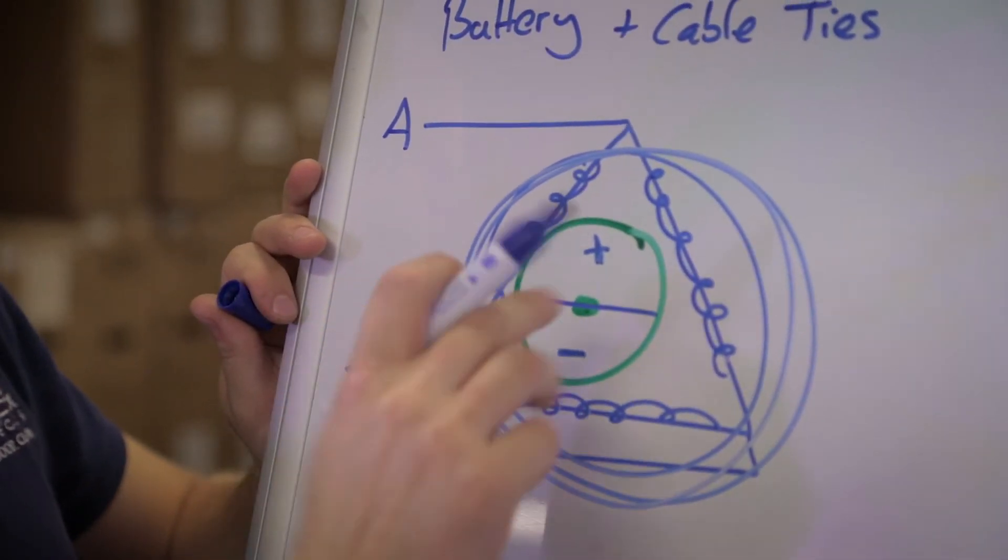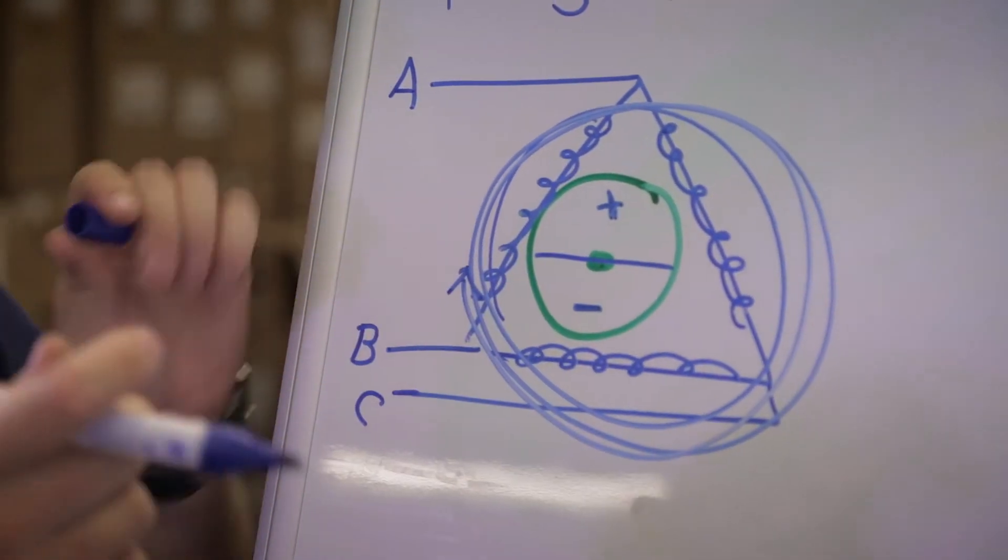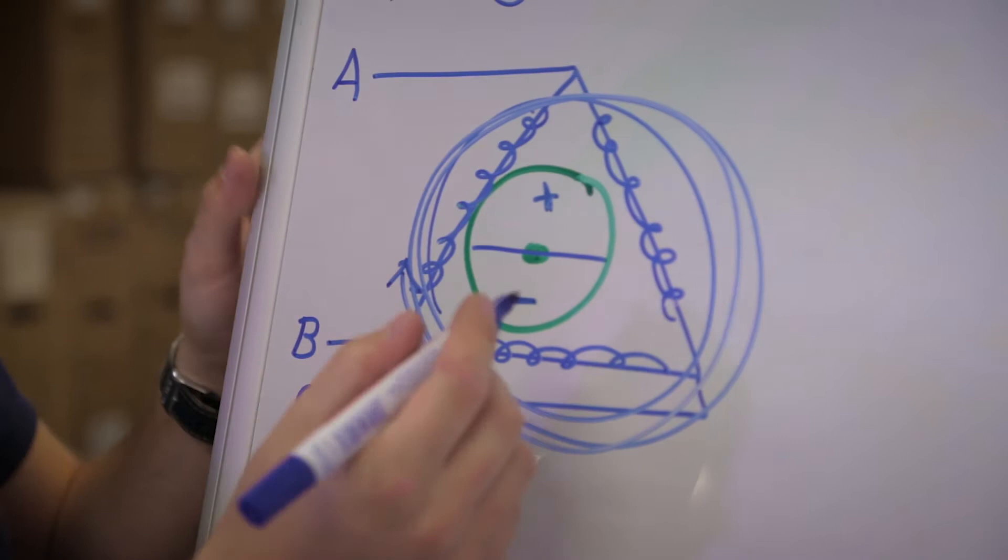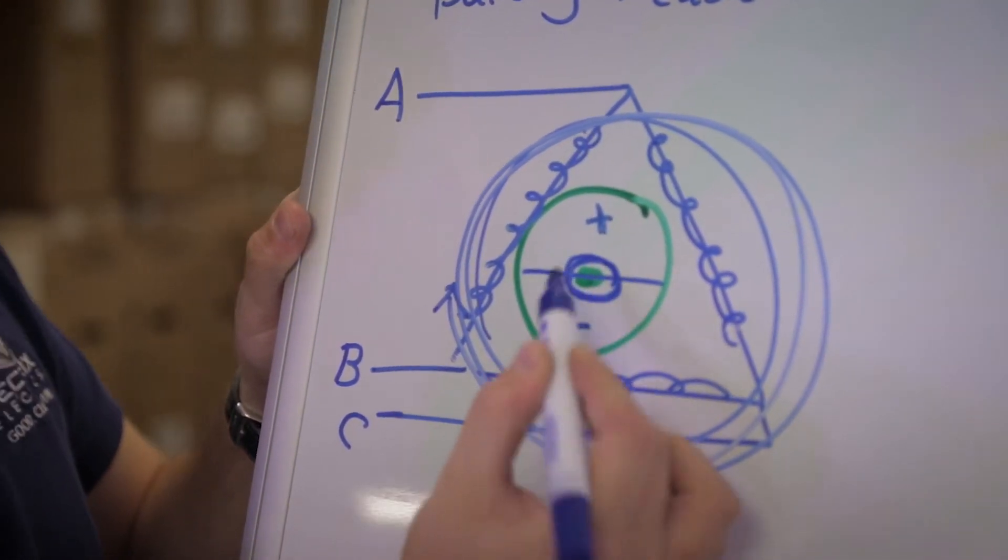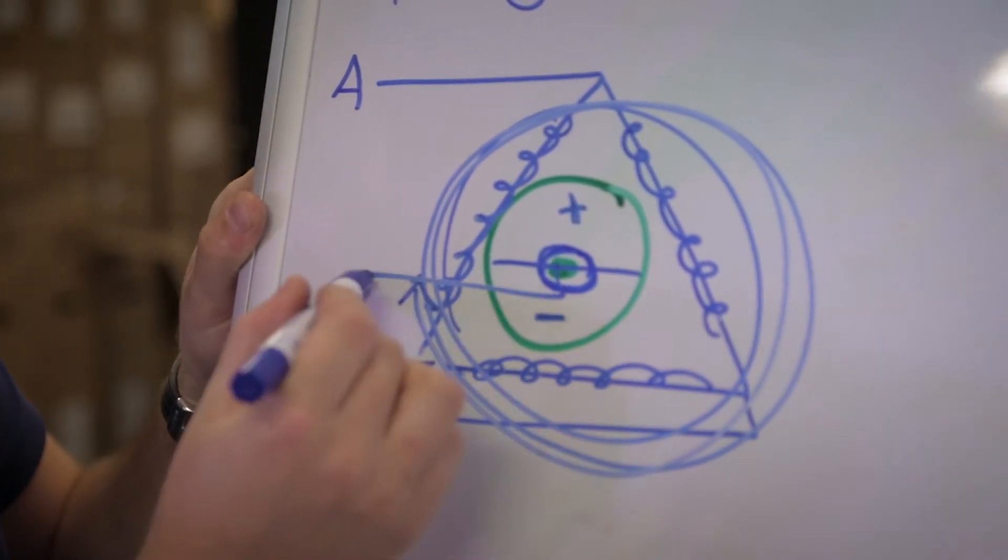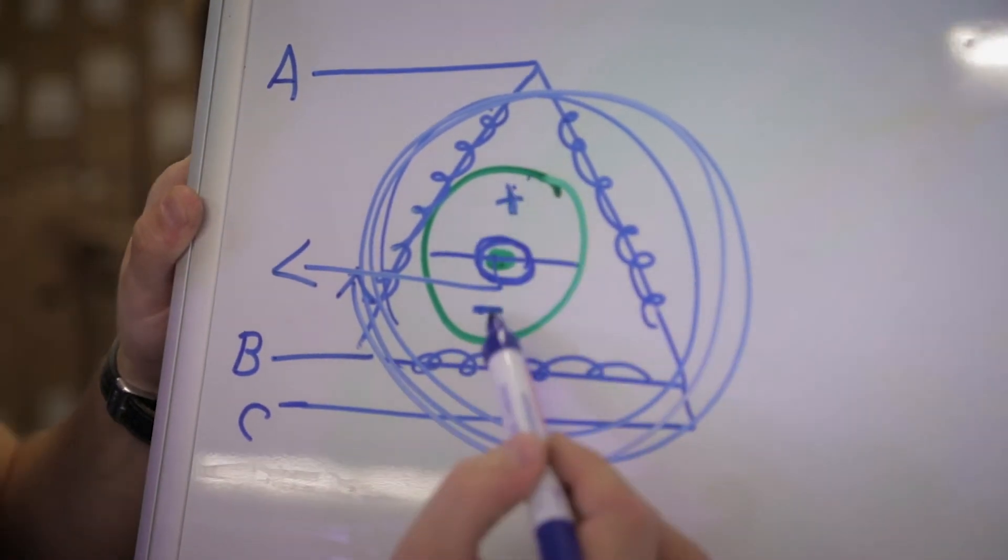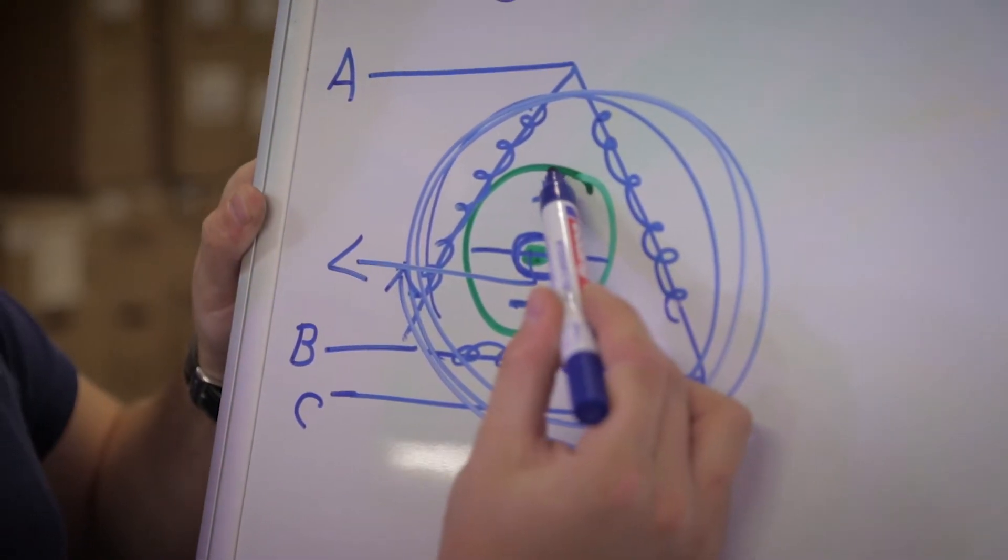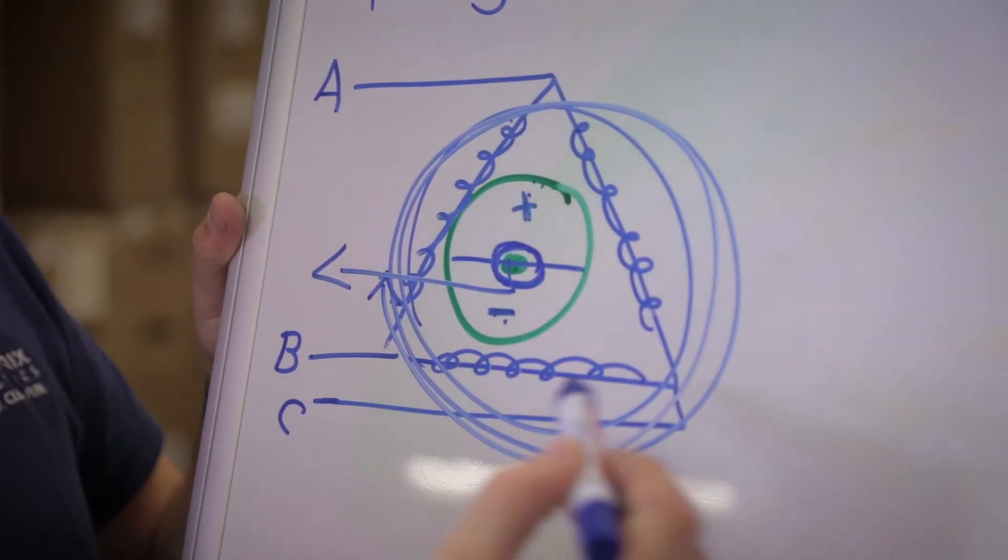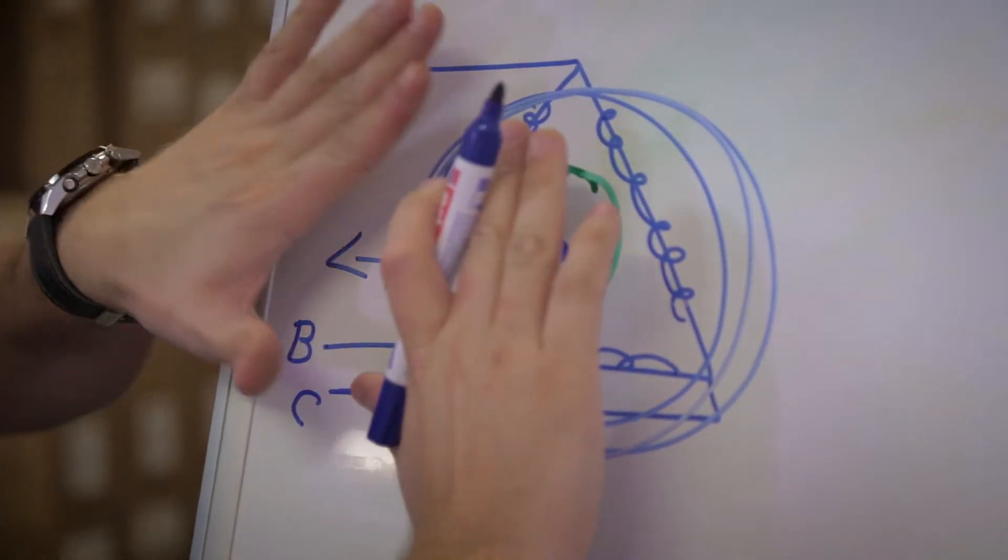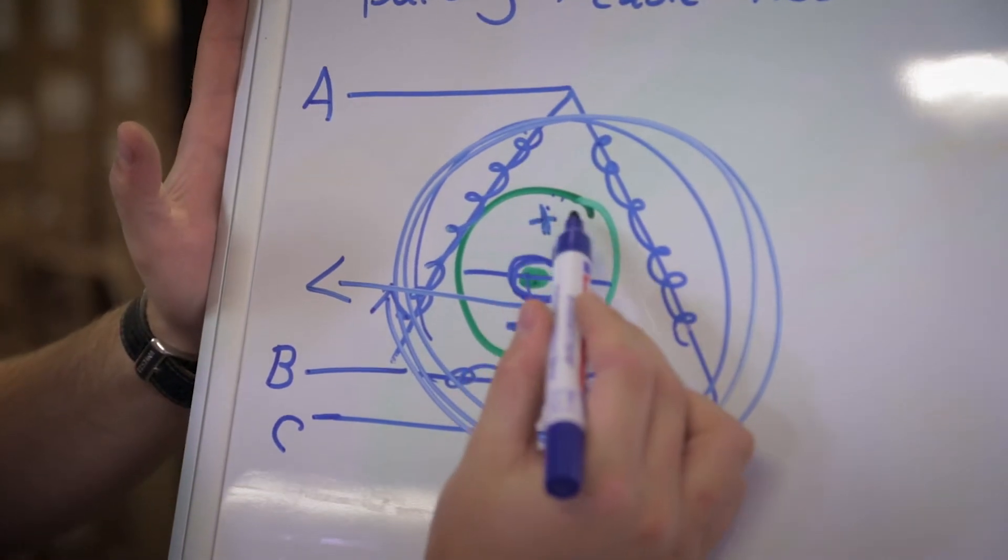And the rotor, because it's polarized, it will just try to follow it. It will spin. Now the modern motor has a sensor mounted here on the shaft that provides feedback to the motor controller about the position of the rotor magnets in reference to the status of polarization of the magnetic field. So we know exactly that we have to switch to the next step when the plus will be here or here, here, here. So it's an absolute position feedback.